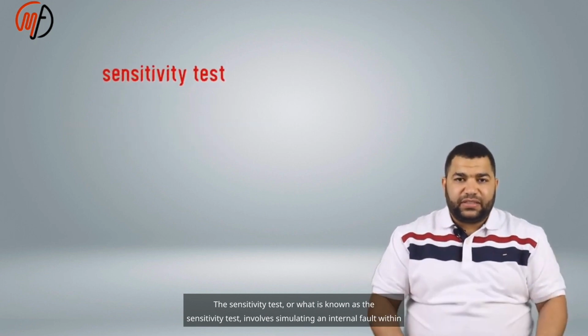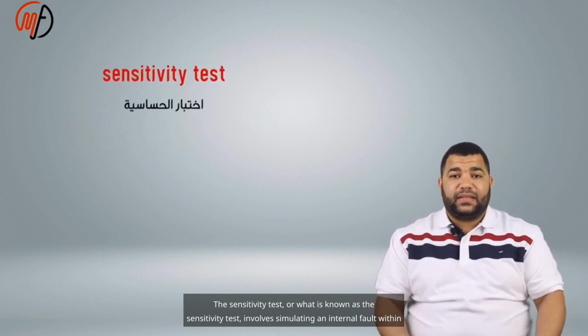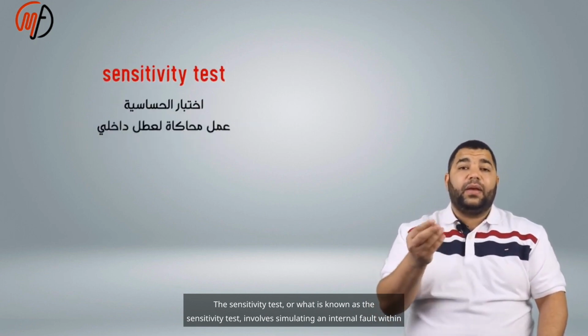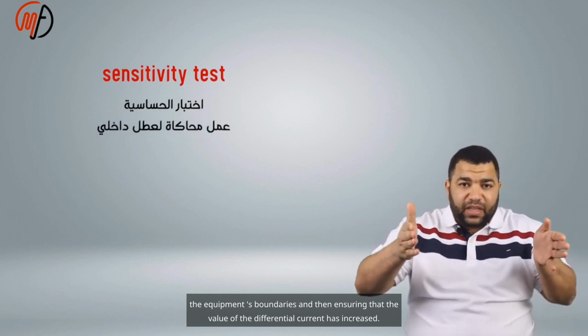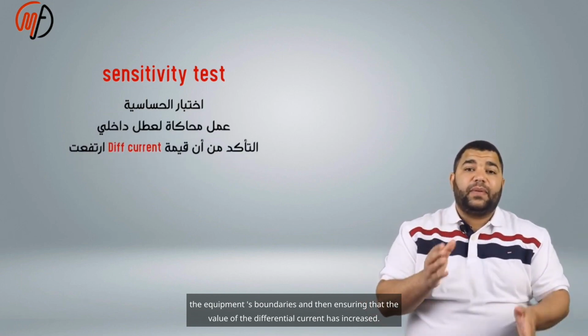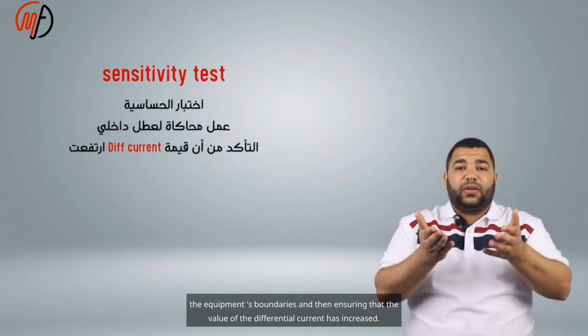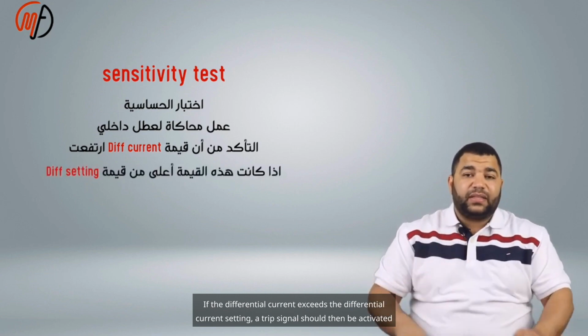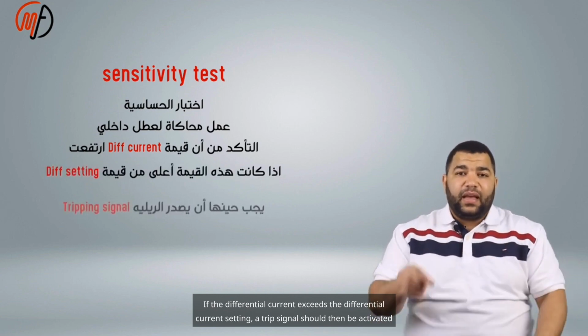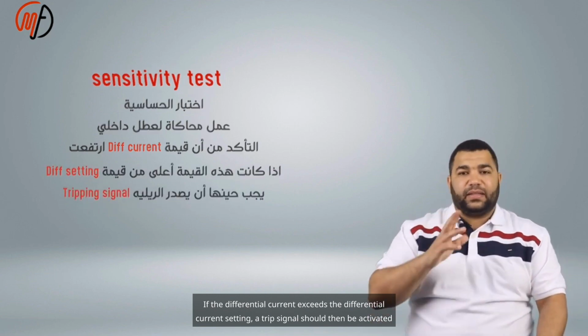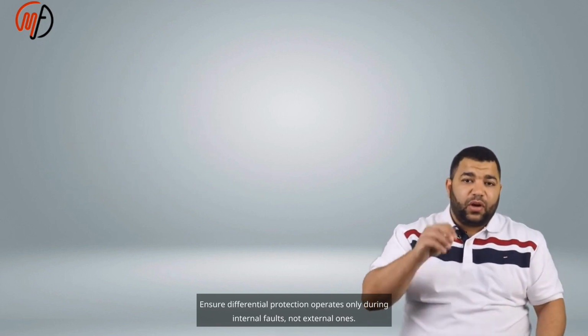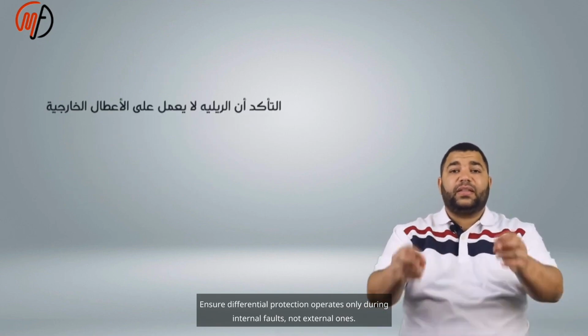The sensitivity test involves simulating an internal fault within the equipment's boundaries and then ensuring that the value of the differential current has increased. If the differential current exceeds the differential current setting, a trip signal should then be activated. Ensure differential protection operates only during internal faults, not external ones.